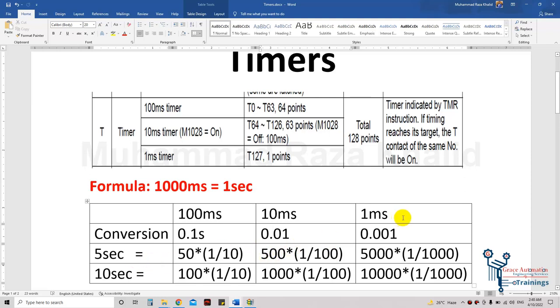If we want to use a 1 millisecond timer and count for 5 seconds, we must write 5000. Because 1 millisecond equals 0.001, which is 1/1000 — cutting all three zeros leaves 5, so it runs for 5 seconds.